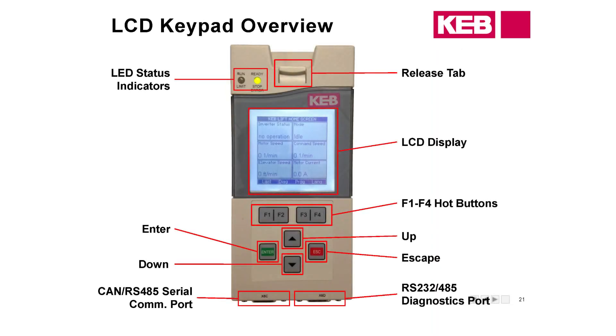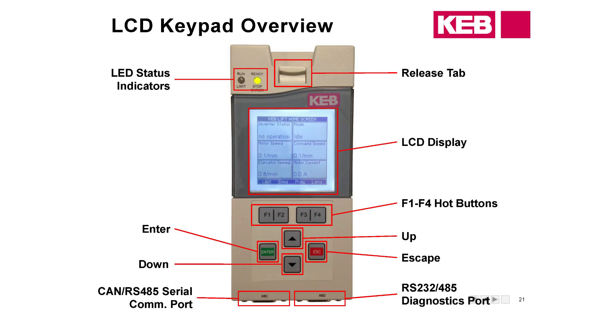Moving on to the LCD keypad — we've increased the size of the screen and added a few extra buttons as well as some diagnostic ports, all of which help with troubleshooting and make setting up the drive much easier. X6D is the diagnostic port for plugging in your cable if you have the inverter programming software Combivis 6. X6C is the CAN or RS-485 serial port for connecting to your controller for serial speed control. We also added F1 through F4 hotkeys that provide advanced menu options and additional functionality.